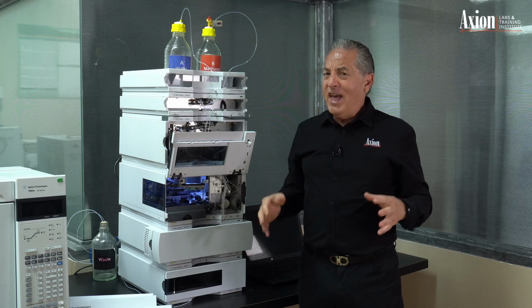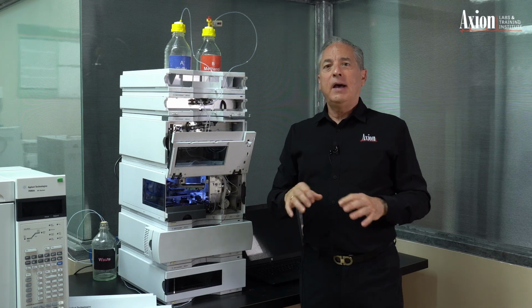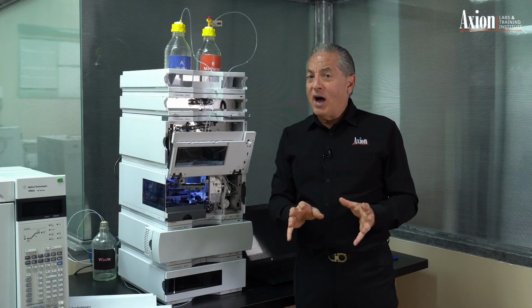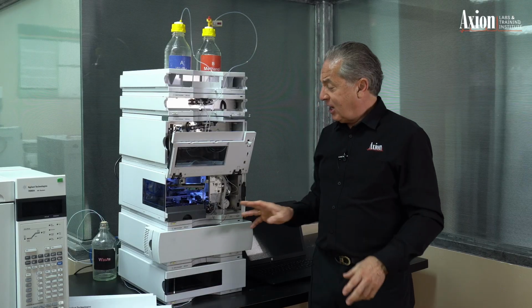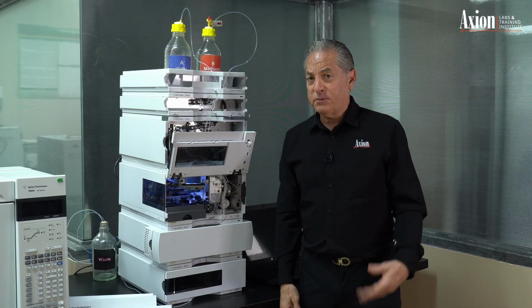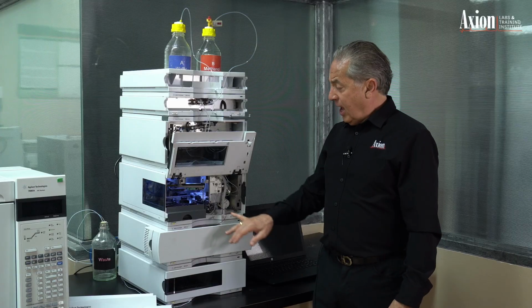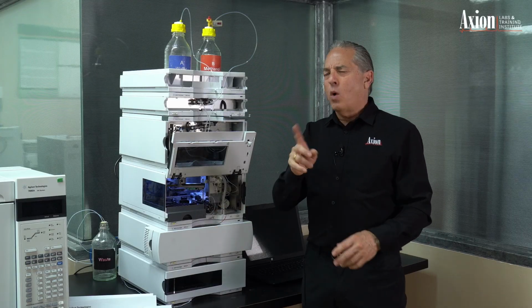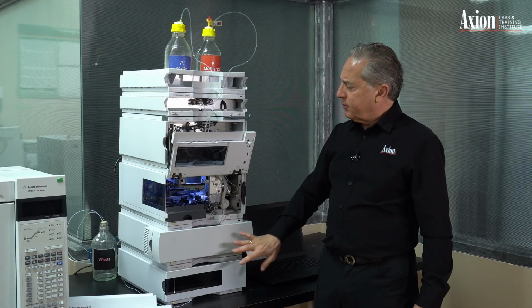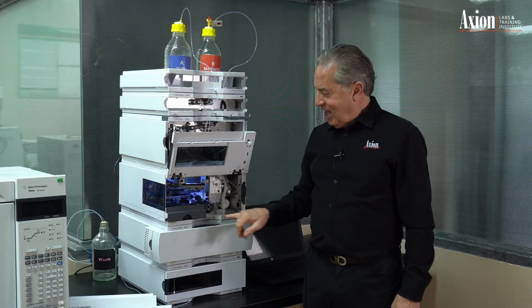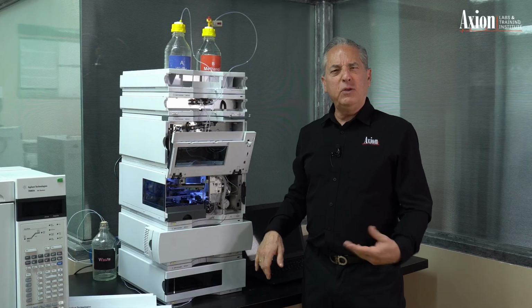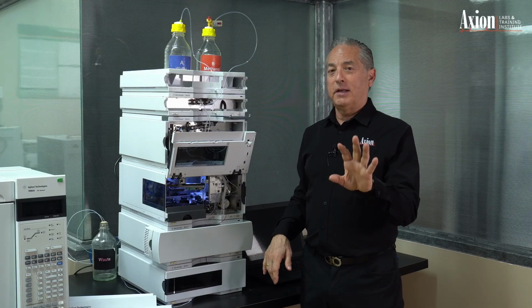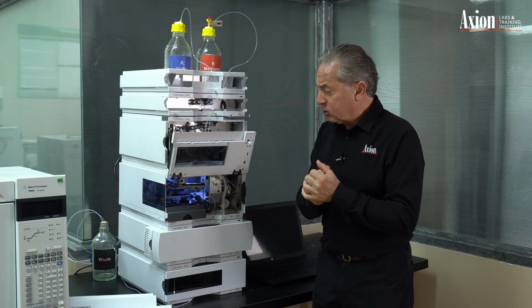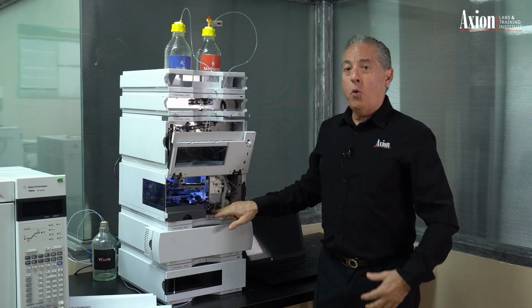Now, the injection valve has a lot of intricacies to it. I have a separate video on that, so if you want to see the details, check out my detailed explanation of the sample injection valve, because on the inside, there's one part that's going to wear out, and the whole autosampler is only one piece you'll ever have to change, and that's the rotor seal. And when I do the deep dive, I'll explain why it goes bad, and I'll show you the little pictures as well.